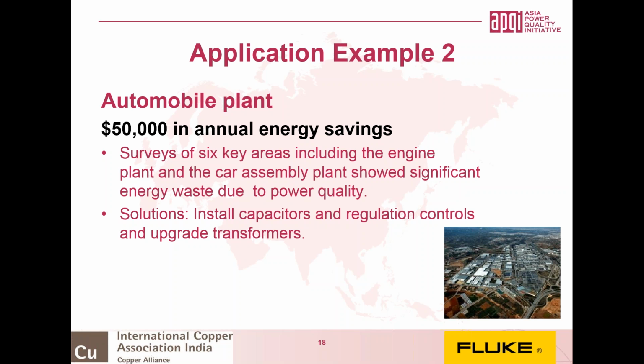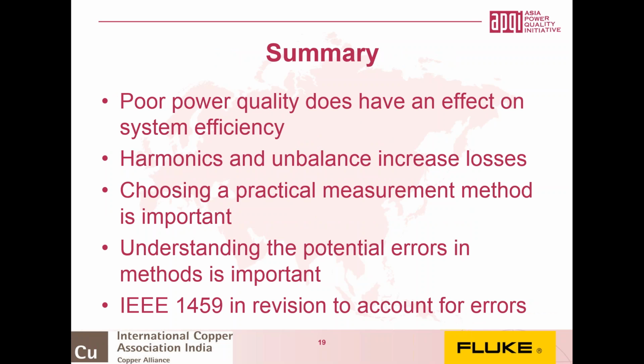So, quick summary: poor power quality does have an effect on system efficiency. Harmonics and unbalance increase losses. Choosing a practical method is really important, because you want something which is not going to take up too much of your time, that you can understand what's going on, and you can pinpoint the areas where savings can be made and efficiencies can be taken out. Making sure that you're using the right method and recognizing that there are potential errors in your calculation method is important. And to that end, IEEE 1459 is being revised to account for those errors.